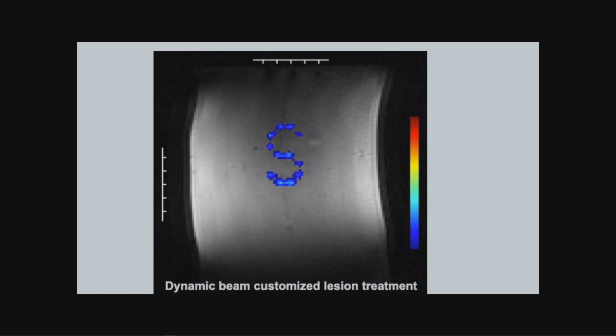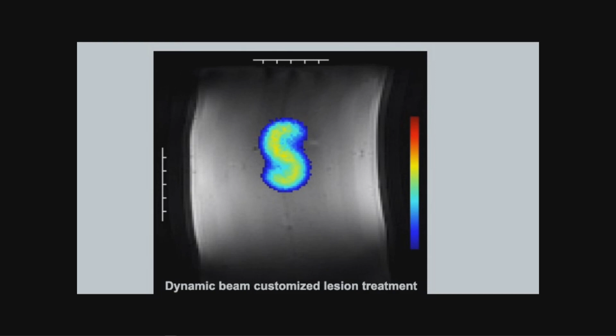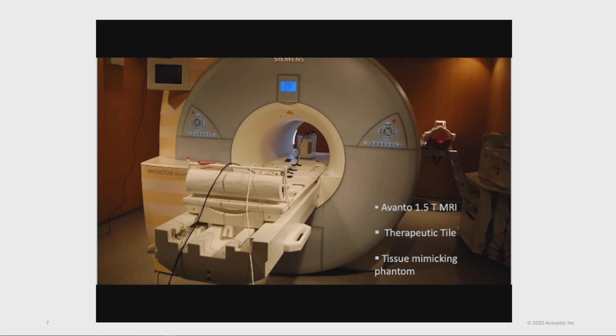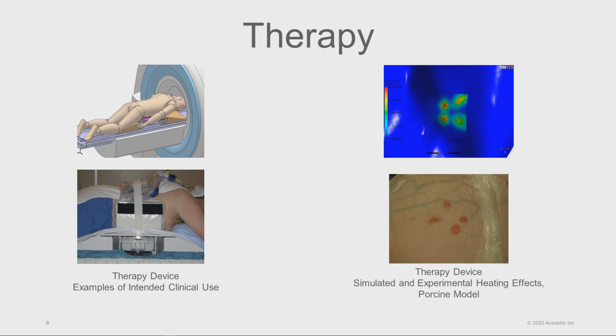This system has been tested within an MR, and you can see the temperature monitoring of the target within the MR, as it forms a recognizable S-shape made up from multiple lesions. In clinical use, our current system is placed in the bed of an existing MR, assembled in a few minutes. The patient lies on top of the applicator and treatment begins. On the right, you can see thermal lesioning as predicted by modeling, along with actual lesioning in a porcine model.